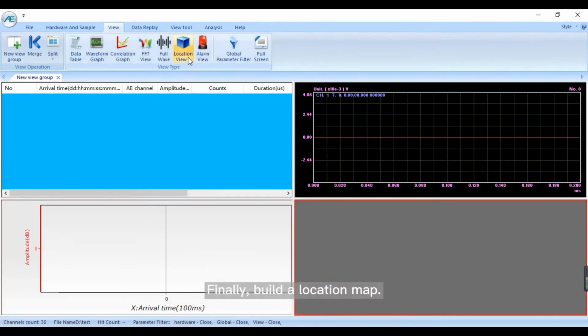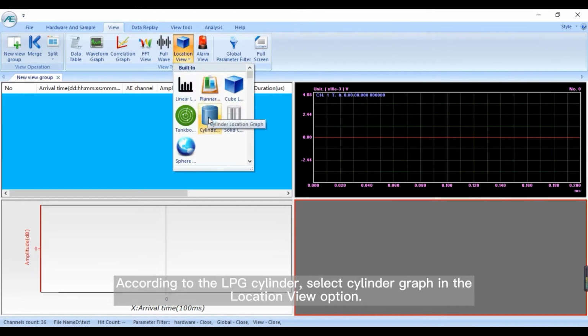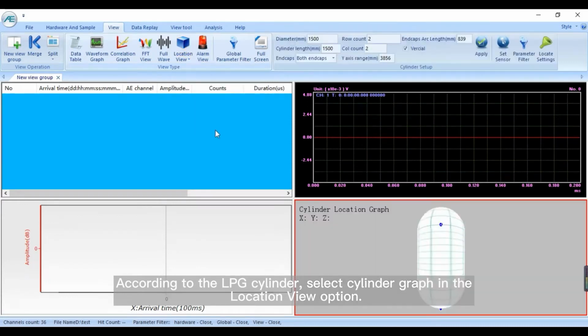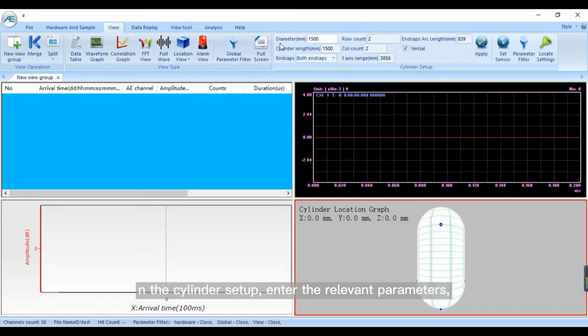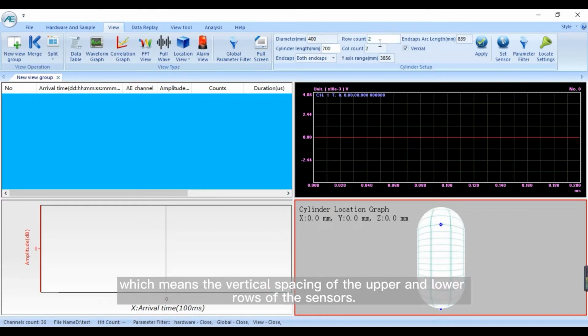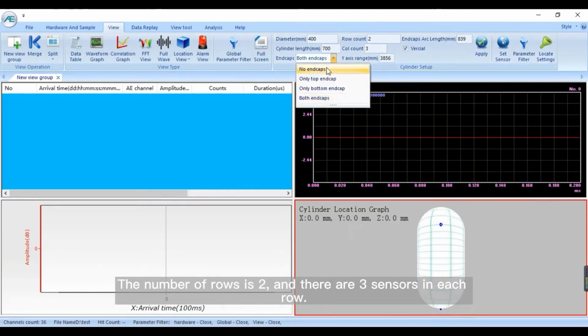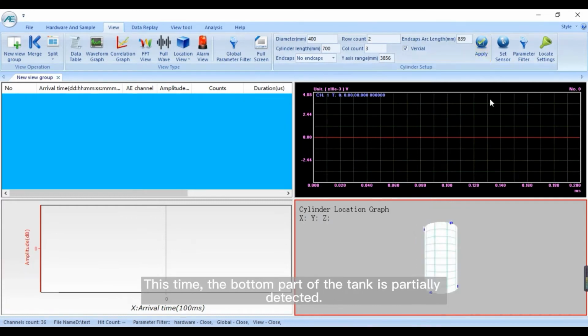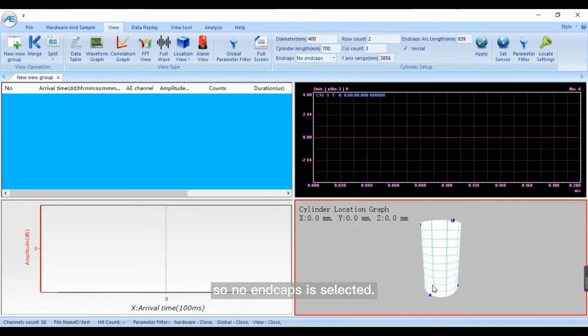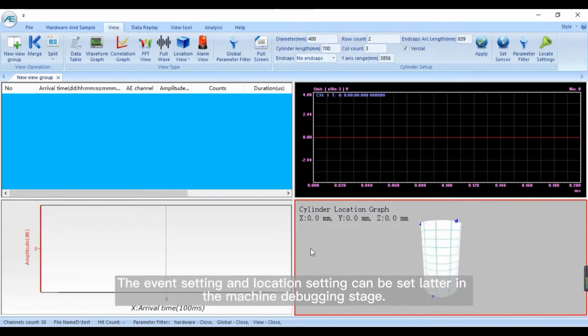Finally, build a location map. According to the LPG cylinder, select cylinder graph in the Location View option. In the cylinder setting, enter the relevant parameters, such as diameter 400 mm, cylinder length 700 mm, which means the vertical spacing of the upper and lower rods of the sensors. The number of rows is 2, and there are 3 sensors in each row. This time, the bottom part of the tank is partially detected, so no end caps is selected. The event setting and location setting can be set later in the machine debugging stage.